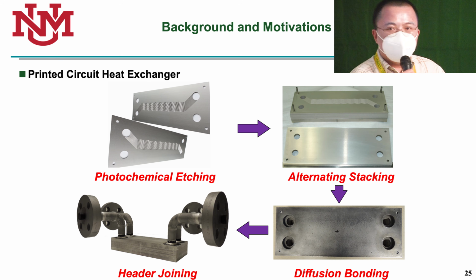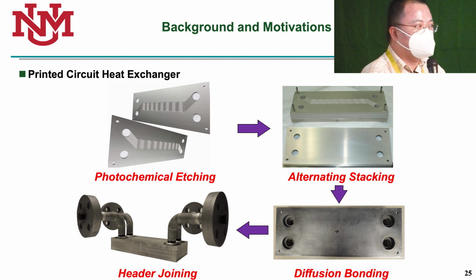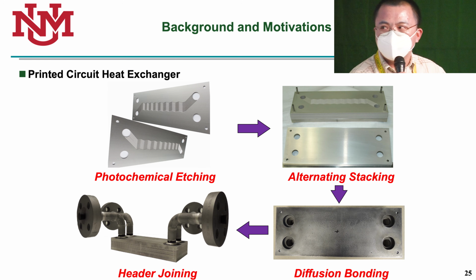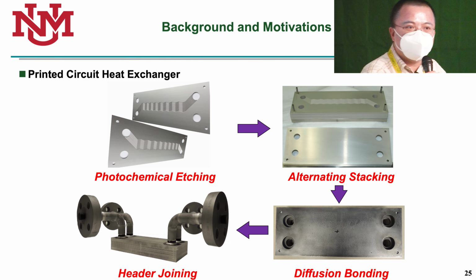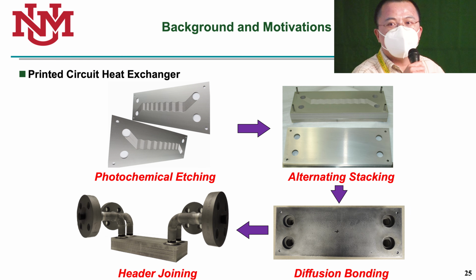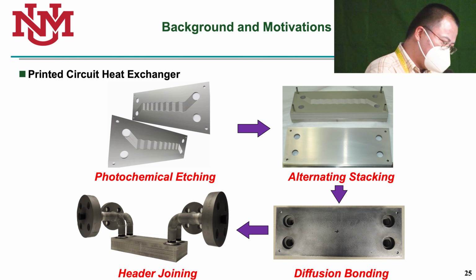What I'm proposing is to use a printed circuit heat exchanger to replace these tubing heat exchangers. A printed circuit exchanger is basically a plate-type heat exchanger with channels chemically etched into the plate. We stack the plates together to get a diffusion-bonded block, and once we've welded the headers on, it gives us a complete heat exchanger.